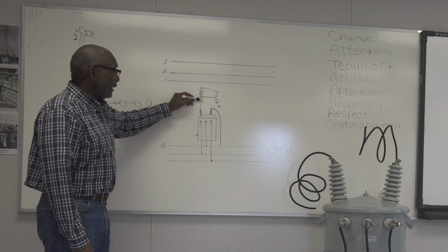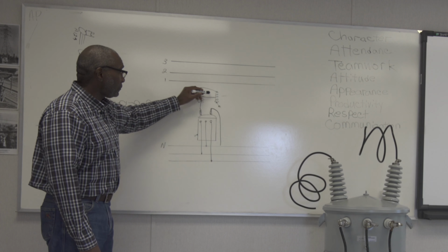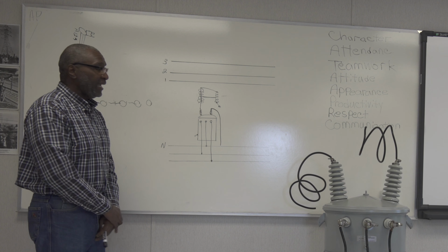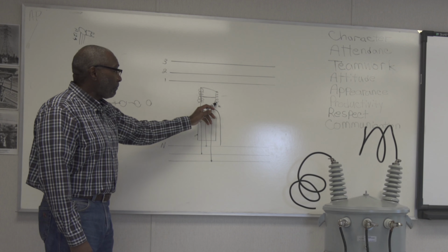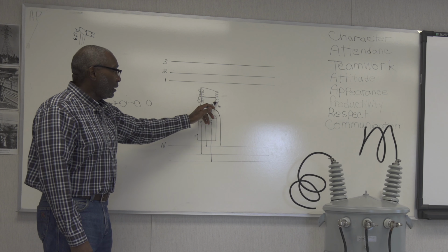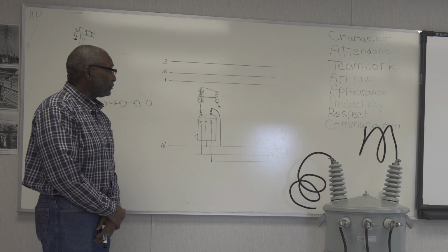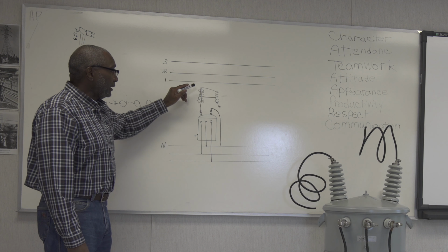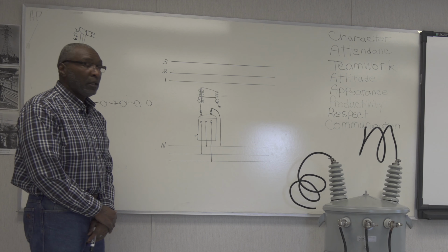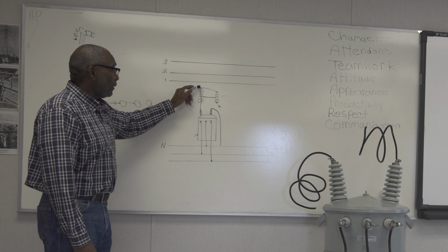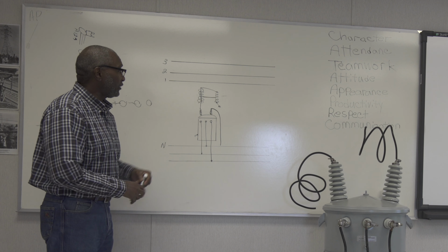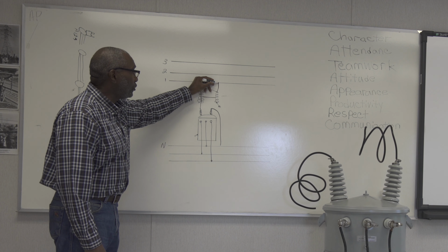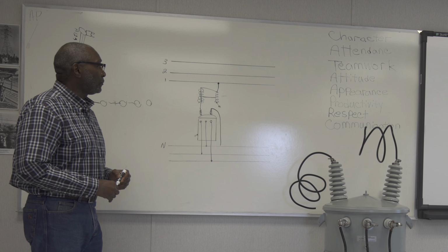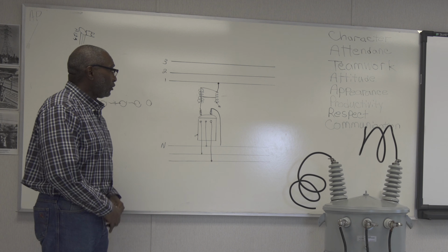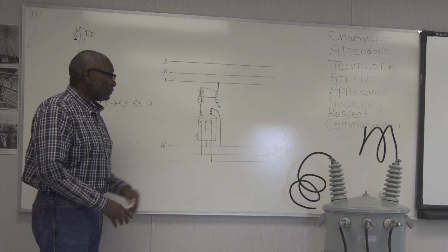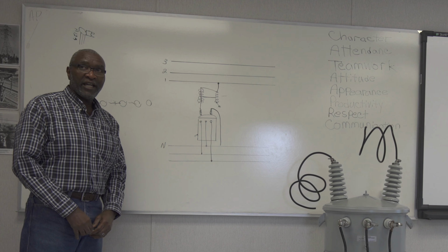This is where your fuse is. Your fuse cutout is here. This is your arrestor. This is indicating your pole ground. This, the bottom of the arrestor, as we've talked about in the field, will be hooked to your pole ground. And remember, building this switch, T-hanger, and arrestor, you always start from the switch side, go over to the arrestor, and then you hook up to your primary. This fuse barrel is open right now. It's ready to be energized.